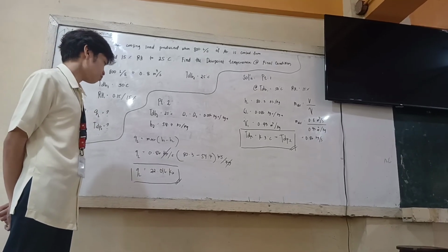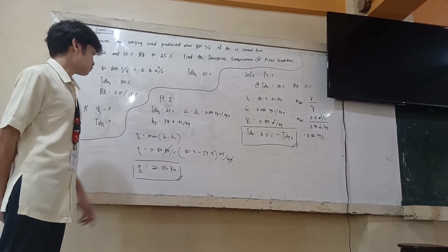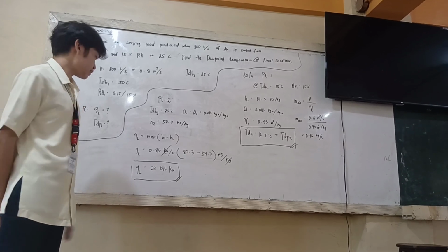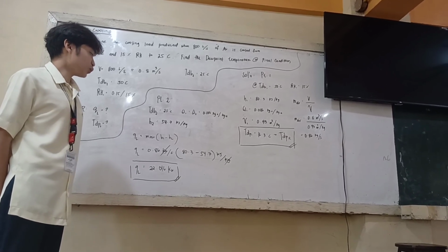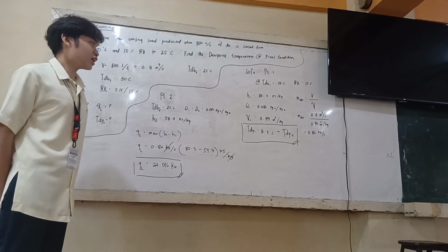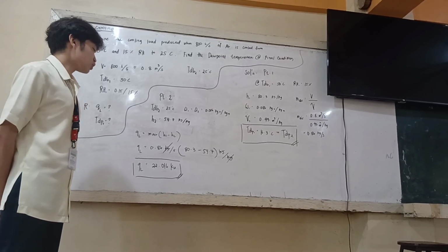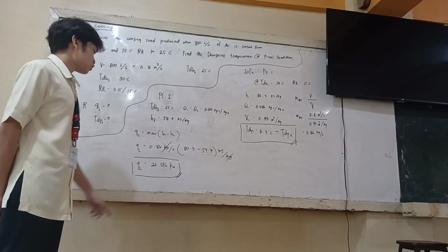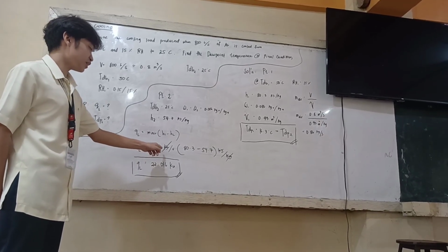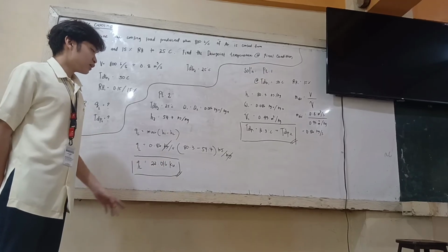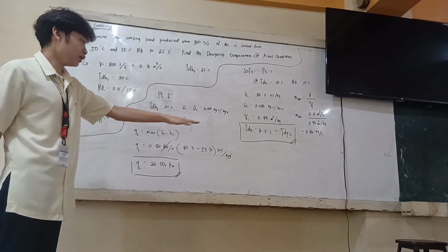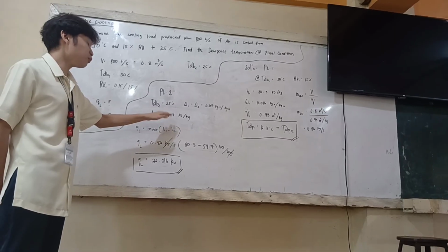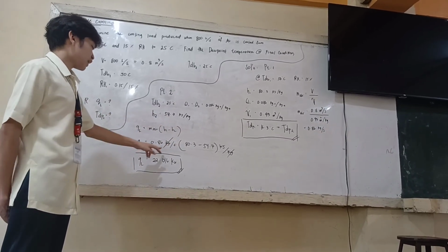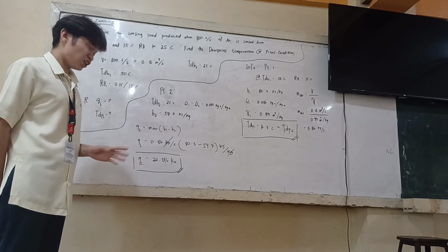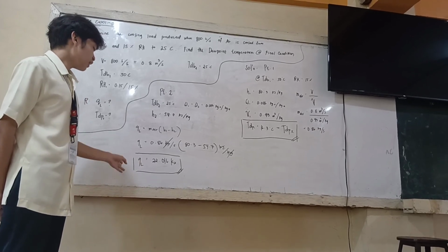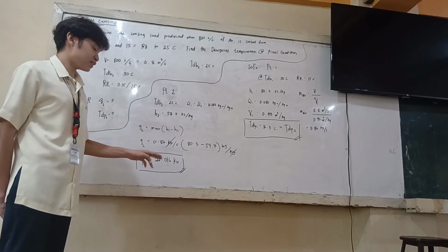Next is the formula for getting the cooling load, which is the mass of air times H1 minus H2. Since we already have these values, we can plug them in: 0.86 kilograms per second times the value of H1, which is 80.3, minus 54.7 kilojoules per kilogram. The kilogram units cancel out, giving kilojoules per second or kilowatts. That results in 22.016 kilowatts.